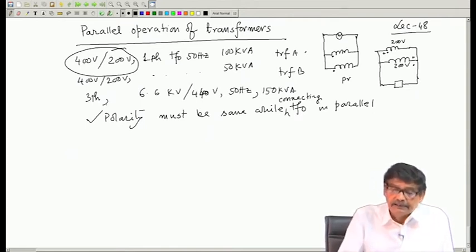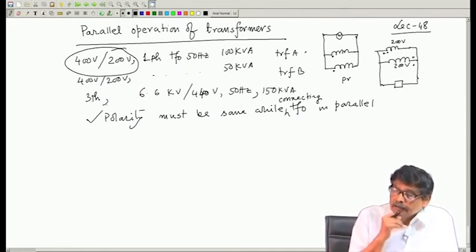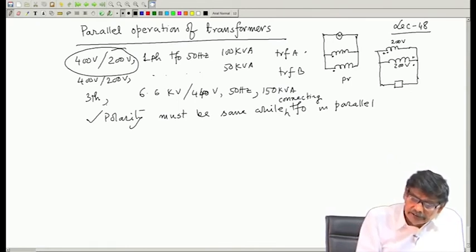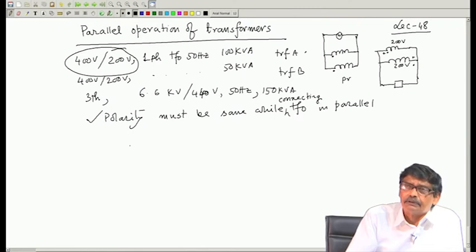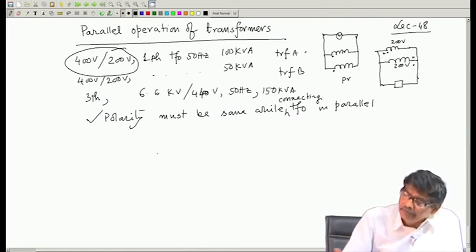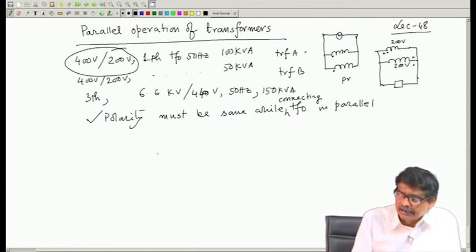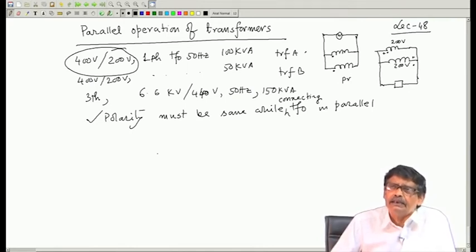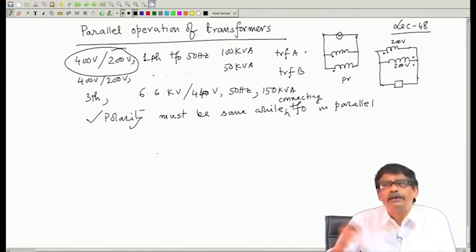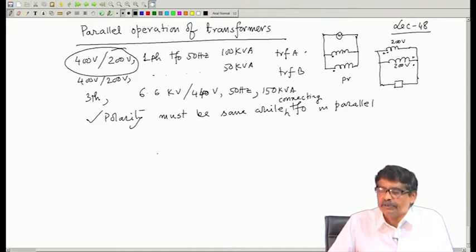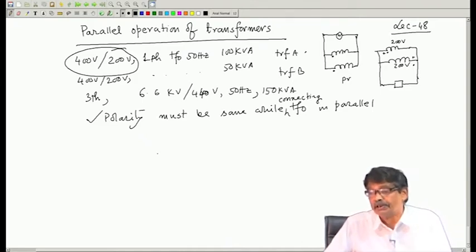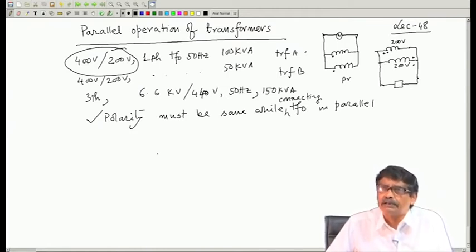Achha. After telling this, there are other conditions which will be clear as we go along. Okay. Now, where to start? It is like this. If you see the connections, I have already told. Now, I will always neglect the no load current in this analysis, no point in taking that. Because no load current is only 5% of the full load current of the given transformers, compared to the load current it is nothing. Therefore, to get a quick and good estimate of the current distributions in the transformers when they are operating in parallel, you better do not take no load current into account.